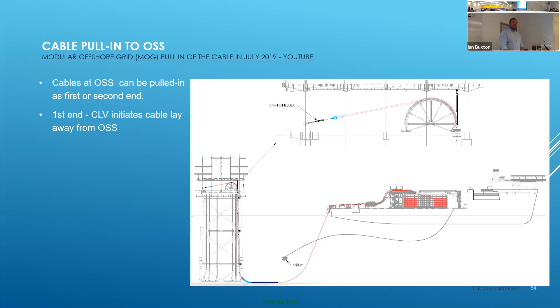Or the slightly trickier option is if you're laying from the landfall end to the substation, you then have to deploy the cable onto the seabed in a bight, and then do what's called a second end pull-in, where you lay the bight on the seabed, you connect your winch on the substation and pull the cable in using the quadrant and the bight to slowly pay out the cable from the quadrant into the substation and hopefully have a nice straight cable route as you approach it.